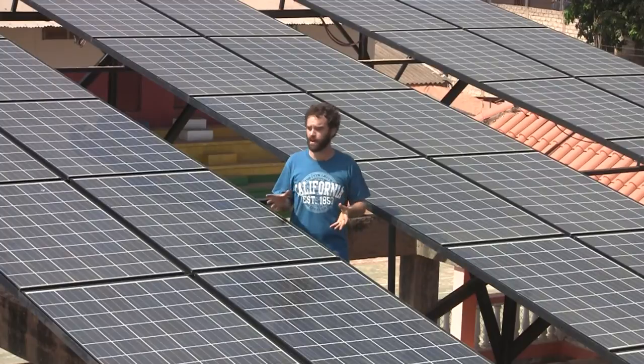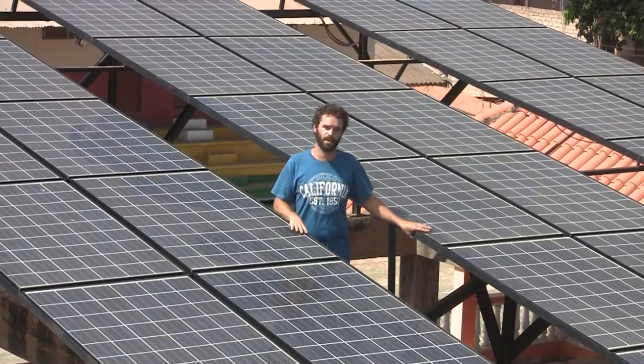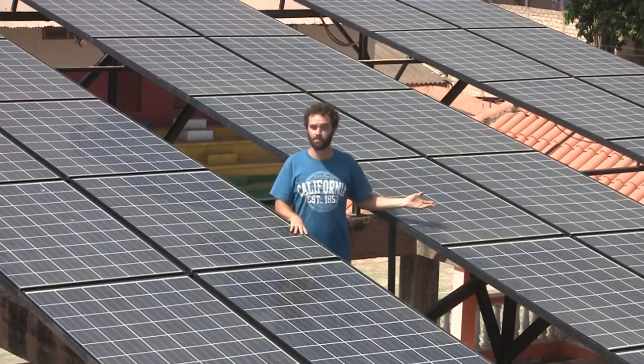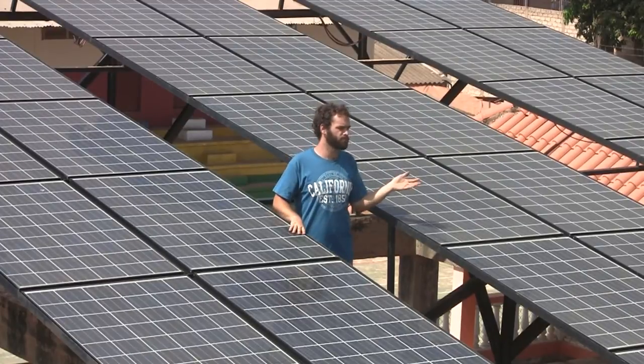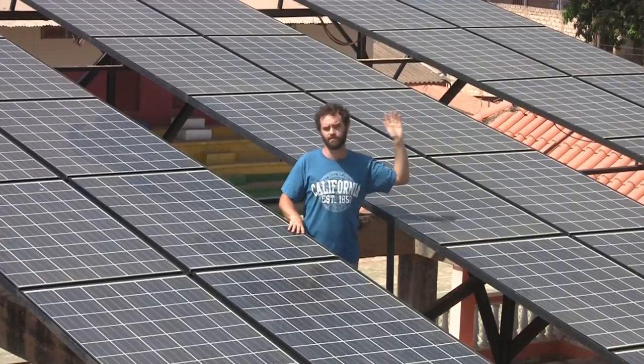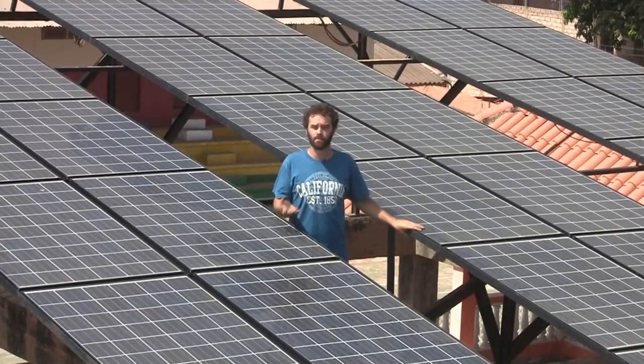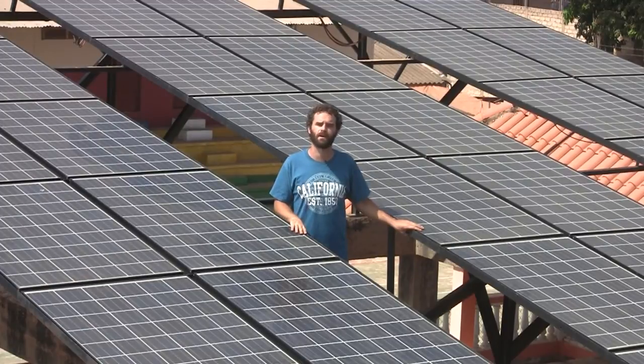The takeaway if you're in a dry season and a dusty place is that you either need to wash the panels every week or so to maintain 90 to 95 percent efficiency, or never bother — because after three, four, or five weeks they didn't appear to lose much more being left to continue on. In the rainy season, with pouring rains every day, we don't bother washing them at all.